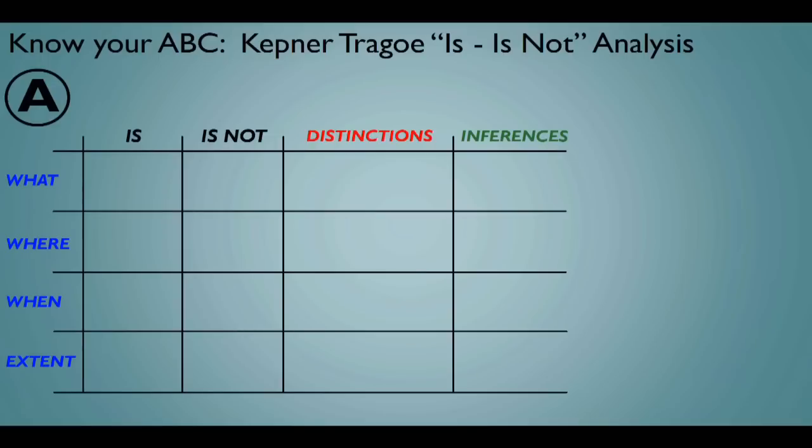You look at what is the problem and what is not the problem. An example might be: if you have cardiac stents and models A, B, and C have worked well, but model D happens to have a lot of issues, then the problem is model D and is not models A, B, C. The distinctions in design are the things to focus on. This doesn't mean you'll immediately find the root cause, but it will point you towards the right factors to investigate.